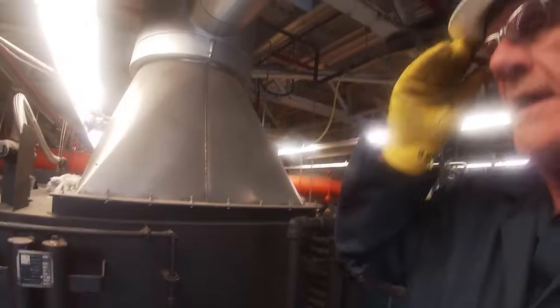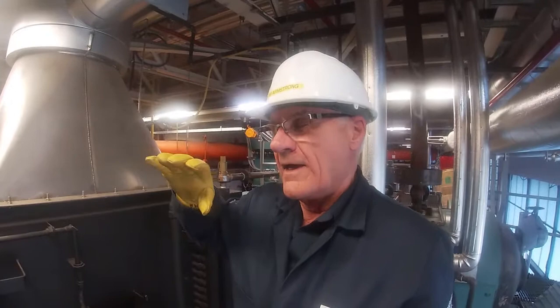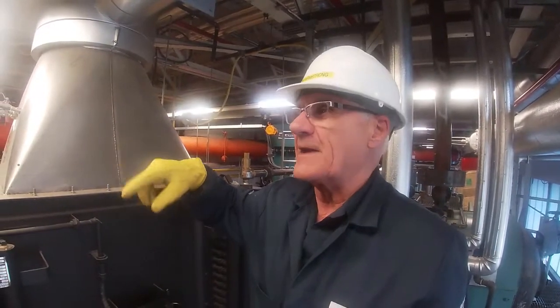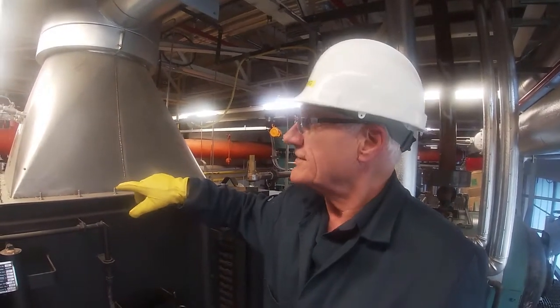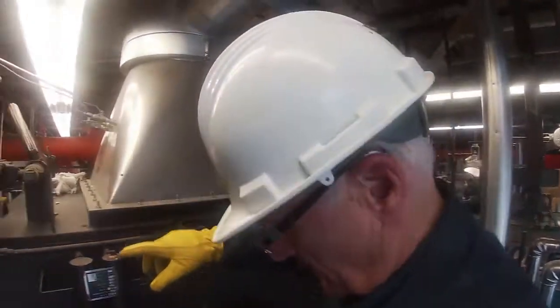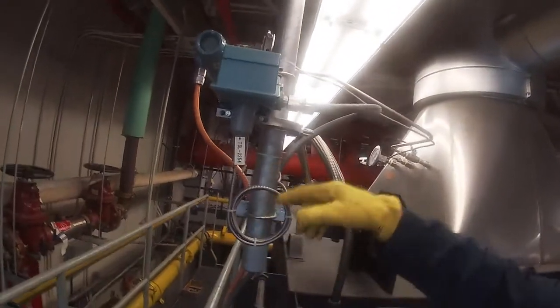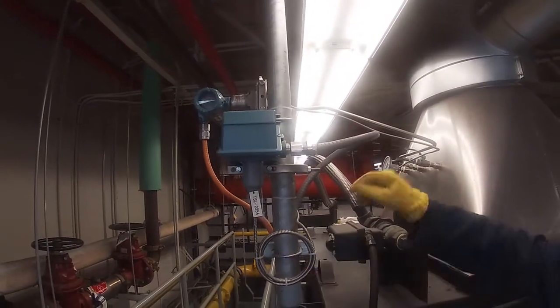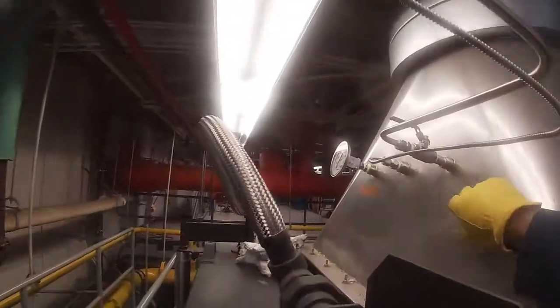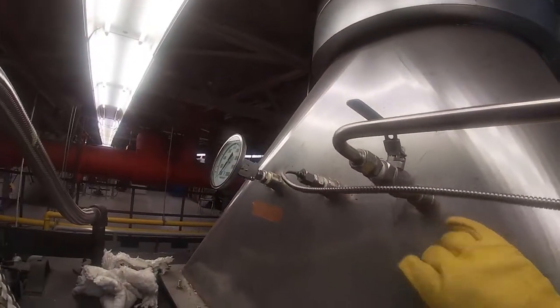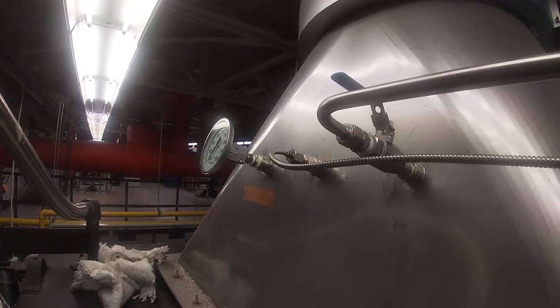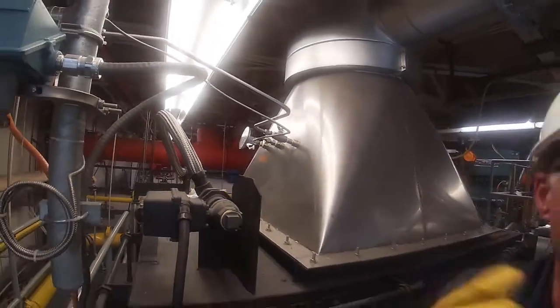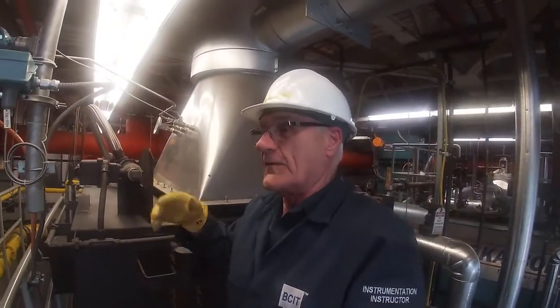gases are hot. And in one of our other videos, you'll see in operating the boiler, we talk about a temperature probe sitting up at the top of the economizer, and the temperature probe is located right here. And this is just a thermal switch, and the sensor is sitting right there, measuring the amount of temperature in the flue gas. We want to get that up to 105 degrees C before we can get a release for modulation from the burner management system. So this is the switch that's got to do it.